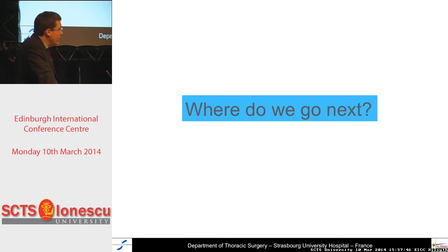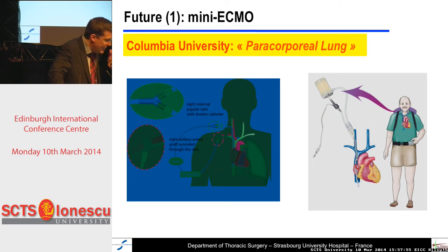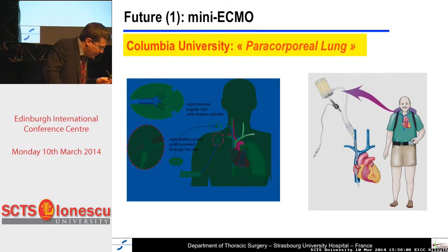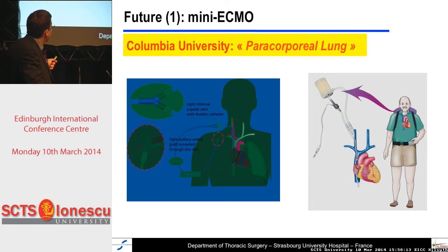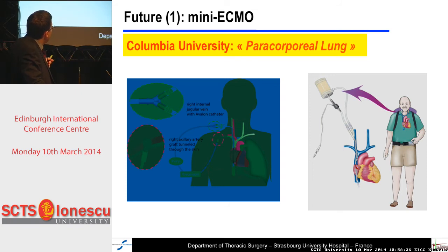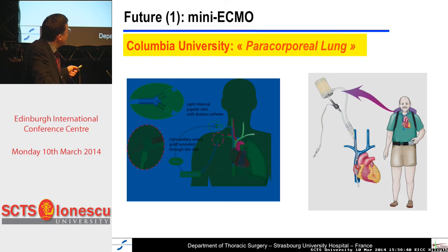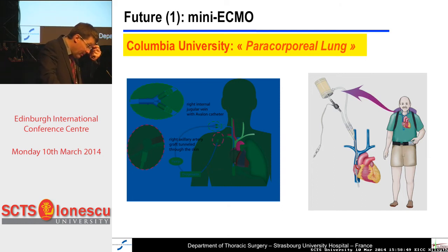Now, where do we go next? First, the mini ECMO — this concept comes from Columbia University and developed the concept of the paracorporeal lung. They use an Avalon cannula for the outflow, derive blood from the inferior and superior vena cava, and after the pump and oxygenator, the oxygenated blood is reinserted via the right atrium. The idea is to reduce the tubing, the size of the oxygenator, and the pump, making it a transportable device as has been done 20 years ago with transportable cardiac assist devices.